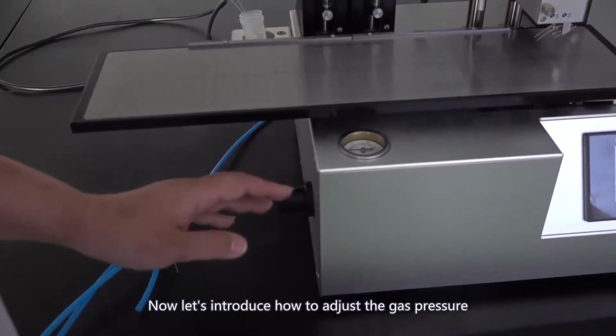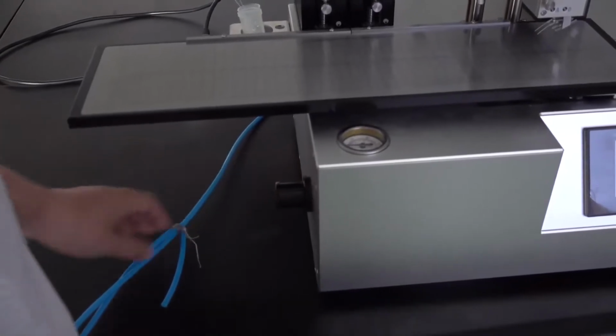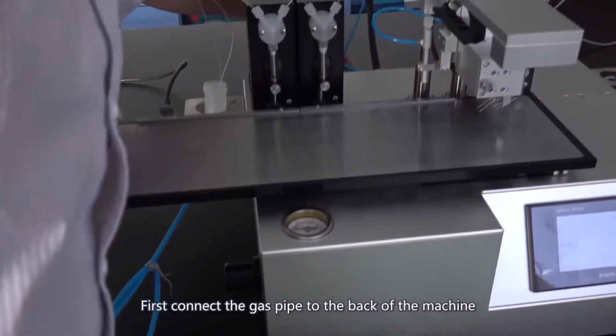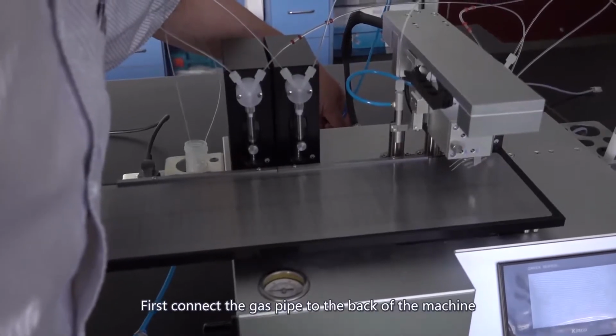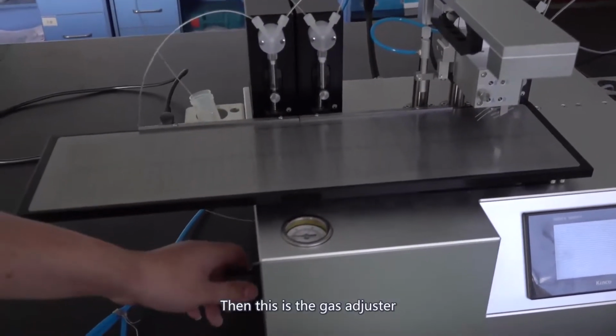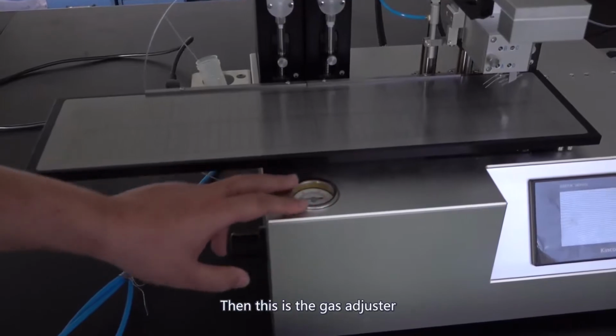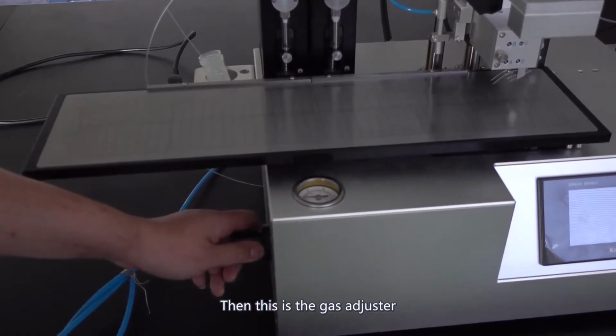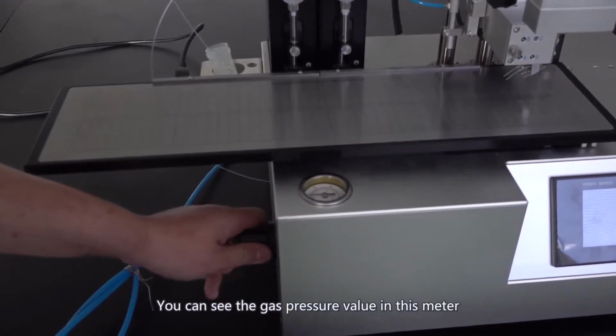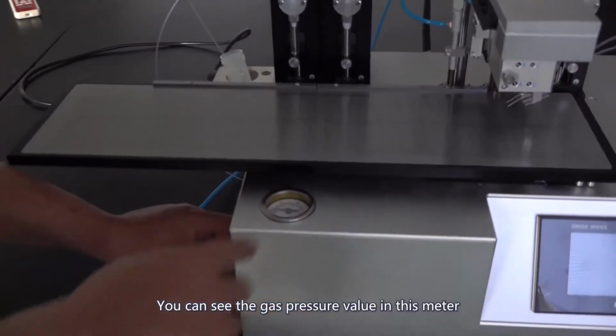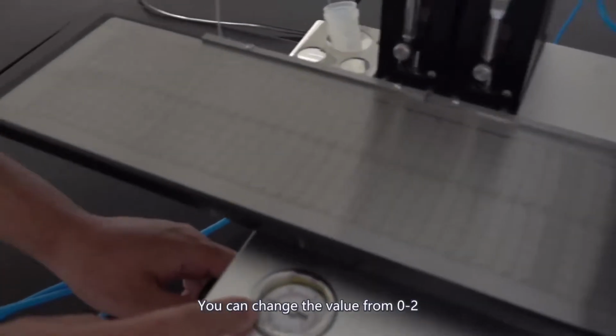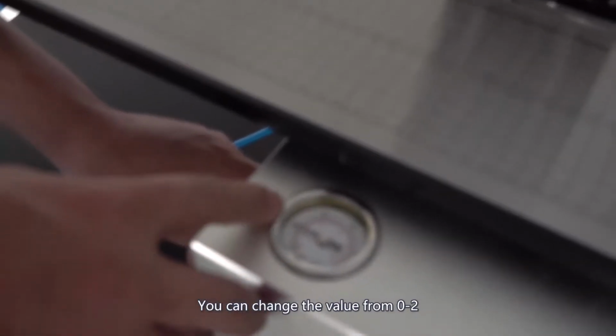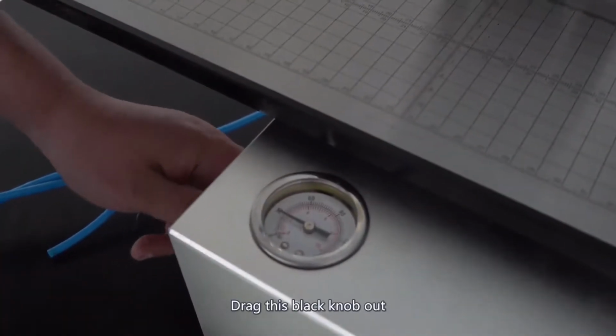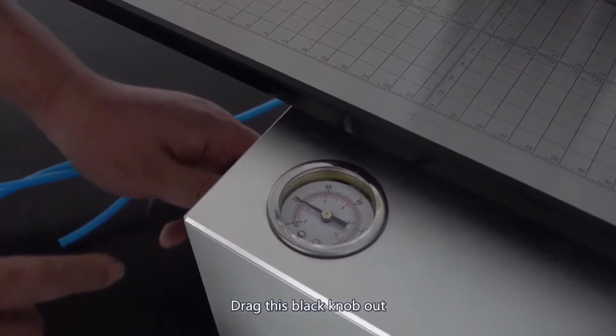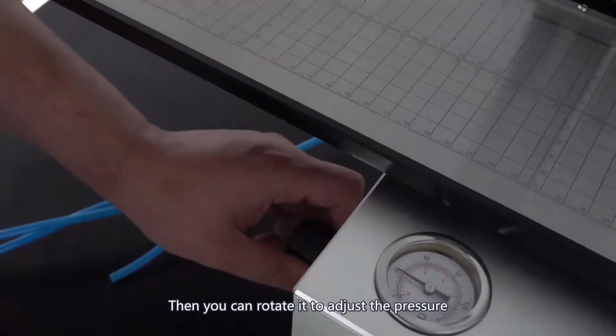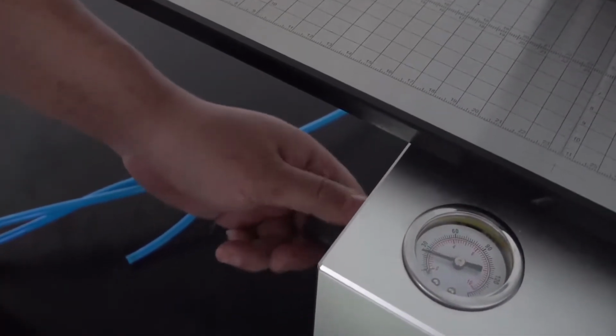Now let's introduce how to adjust the gas pressures. The first is the gas input pipes. Socket in these pipes, and then here are the gas adjusters, and you can see this is the value for the gas. You can change the values from 0 to 2, and you can see there is a holder, pull it out, and you can adjust the handle forward and backward.